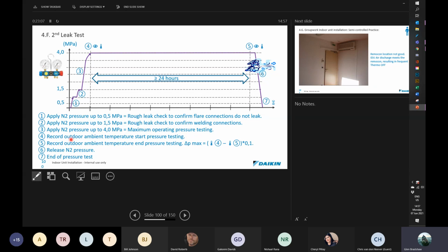Any pressure test always requires you to log the outdoor ambient temperatures at the start of the pressure test, and then record them again on the day that you come to check them, a minimum of 24 hours later, and then check the deviation on there. If you are unsure and you feel that the deviation is borderline, then give it another 24 hours. It's better to do that and lose one more day than end up losing 3 or 4 days having to look for leaks.